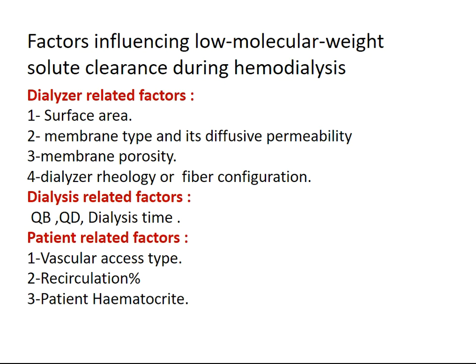Factors influencing low molecular weight solute clearance during hemodialysis include dialyzer-related factors, dialysis-related factors, and patient-related factors. Dialyzer factors include surface area, membrane type and its diffusive permeability, membrane porosity, and dialyzer rheology. Dialysis-related factors include blood flow rate (Qb), dialysate flow rate (Qd), and dialysis time. Patient-related factors include vascular access, recirculation percentage, and patient hematocrit.